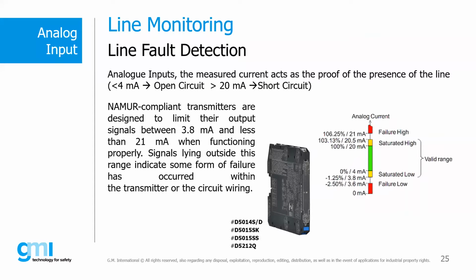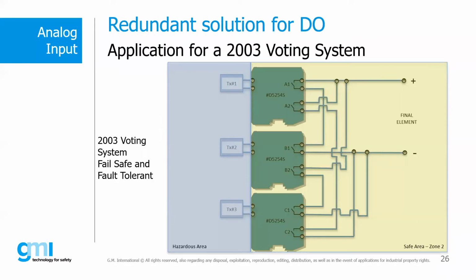Let's now analyze how to obtain a correct system redundancy through trip amplifier devices. One of the typical applications which uses a redundant system with several analog devices is what we can see in the following slide, where a 2 out of 3 redundant system of trip amplifiers is used to activate our final element. This system and its redundant logic allow us to replace more complex systems composed of safety PLC, allowing us to save engineering cost. But let's see specifically.